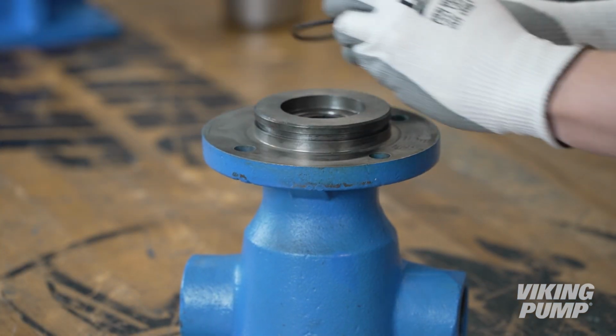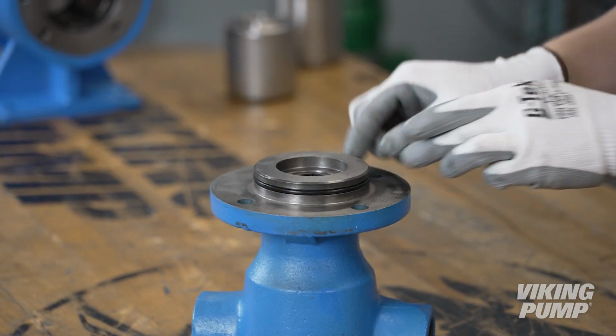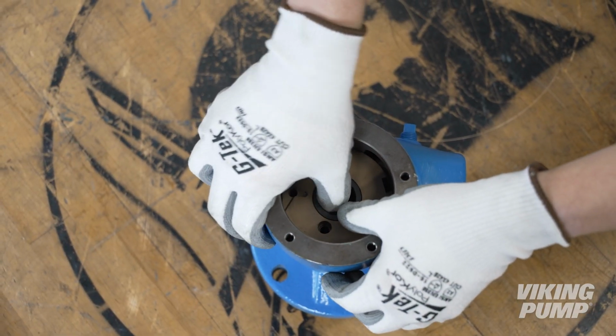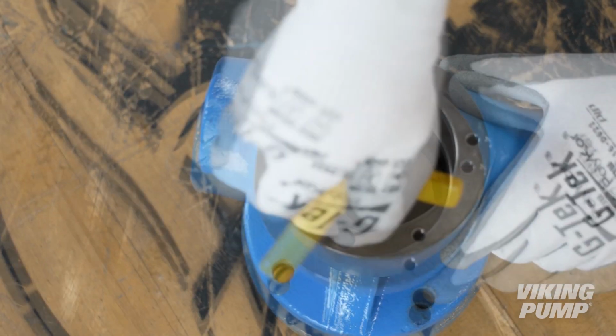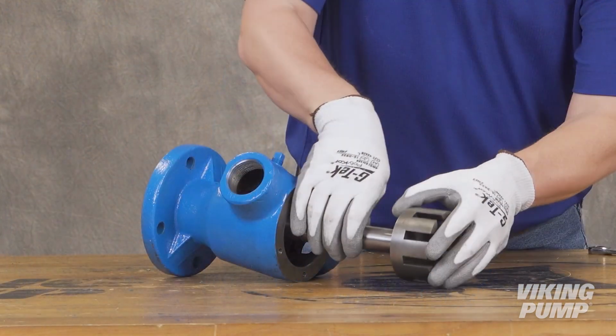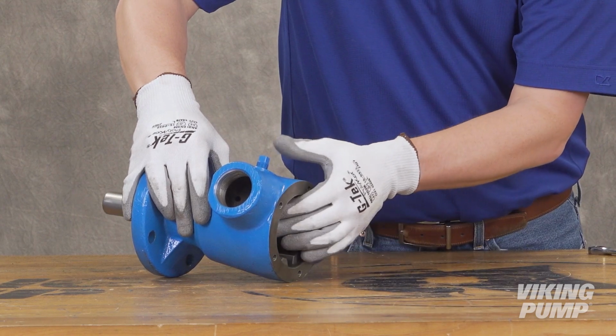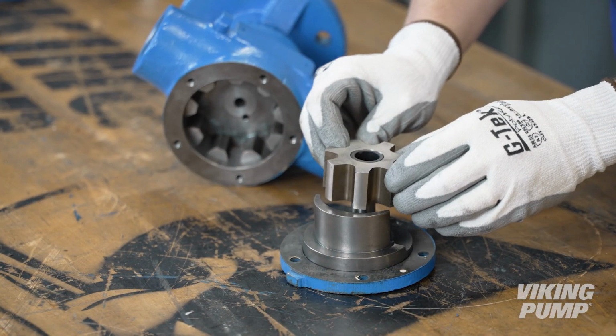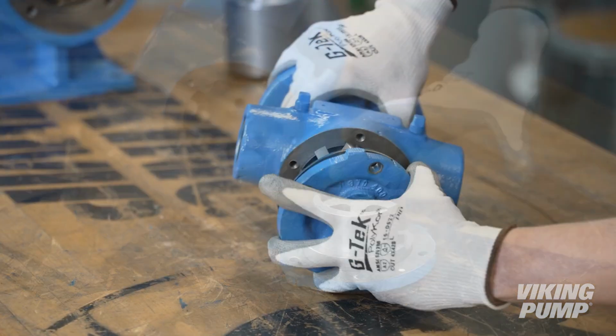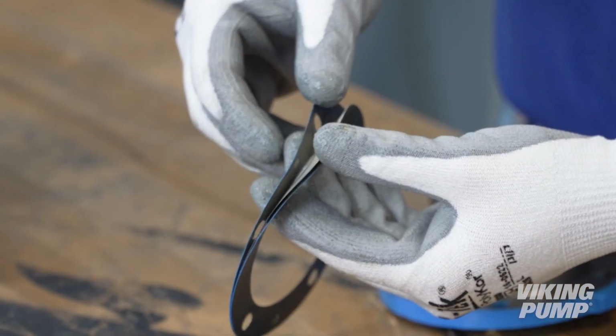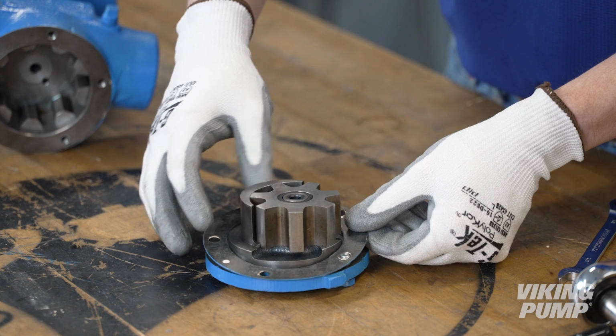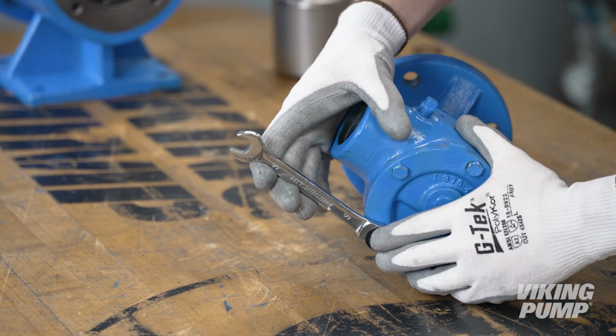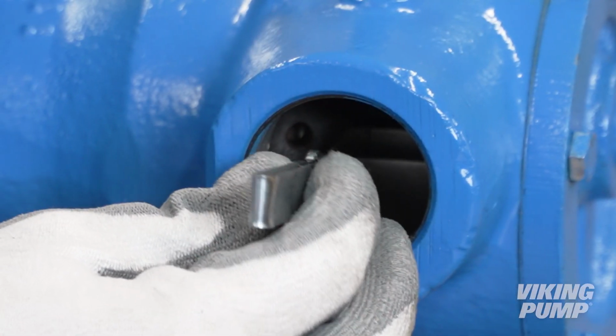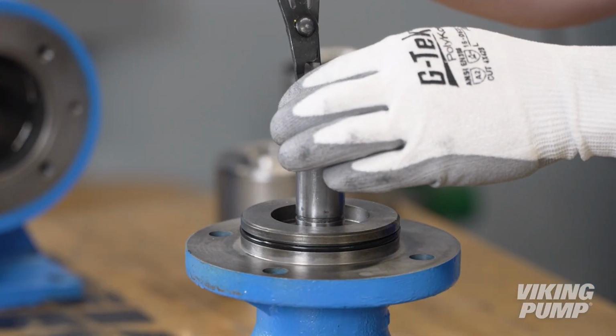Inspect the casing O-ring. Remove and replace if damaged. If removed, reinstall the balance plate. Reinstall the rotor shaft assembly. Next, place the idler gear on the idler pin. Reinstall the head onto the pump, making sure to use the same thickness of gaskets. Reinstall and tighten the head cap screws. Verify the end clearance with feeler gauges. Replace the retaining ring and shaft key.